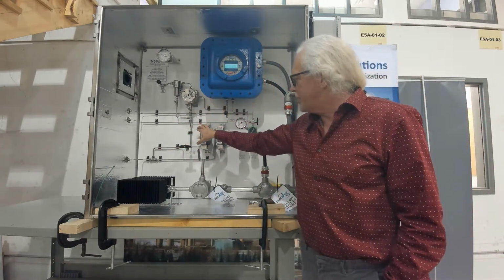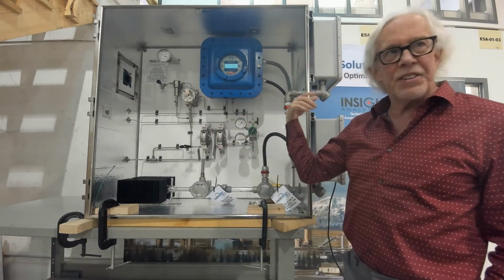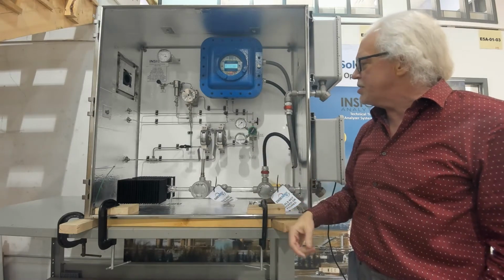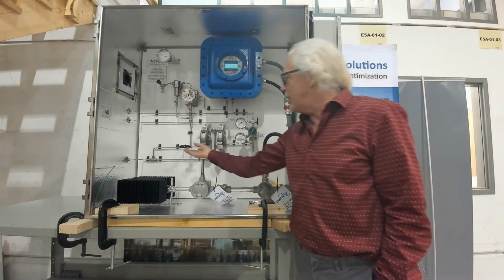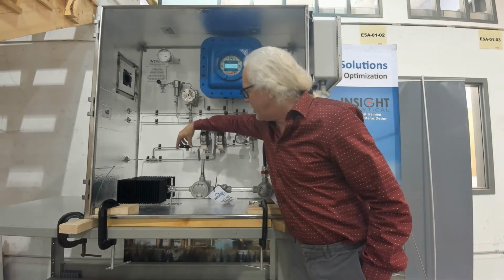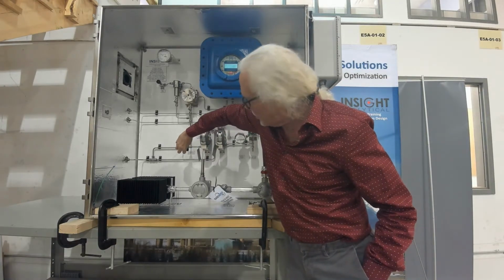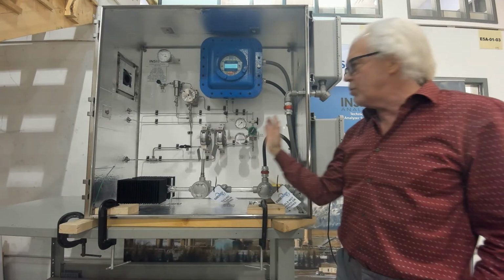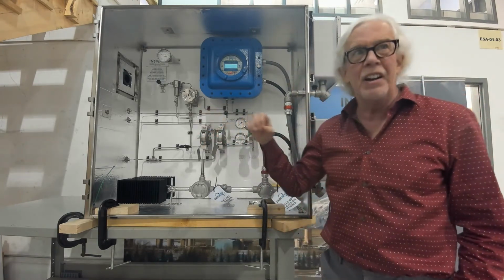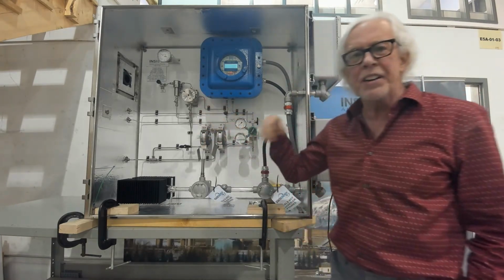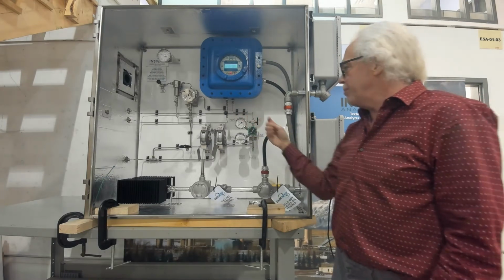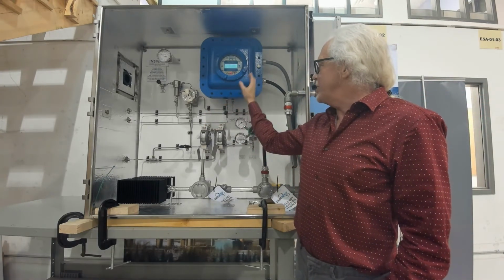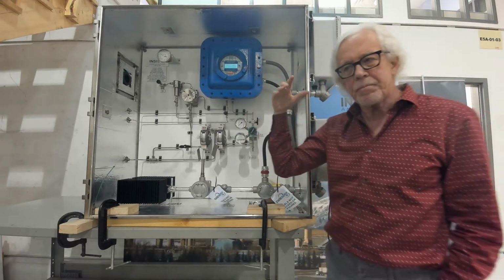We have a bypass flow meter that lets us set up flow rates on the bypass side of those two coalescers. And one of the unique things we do is we have a little dead man's valve here. This is a spring-loaded valve so that we can check the flow of the system and then automatically it returns to bypass the flow meter. This keeps the flow meter from getting wet and getting liquids built up. Flow goes over to the analyzer, where all the work happens.